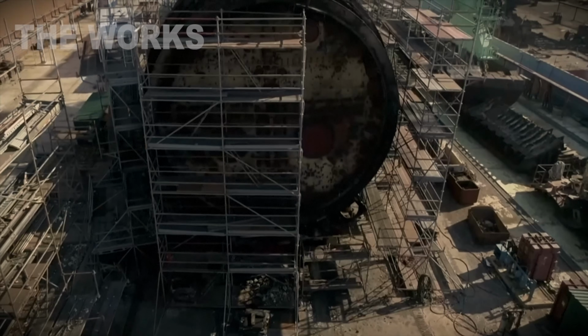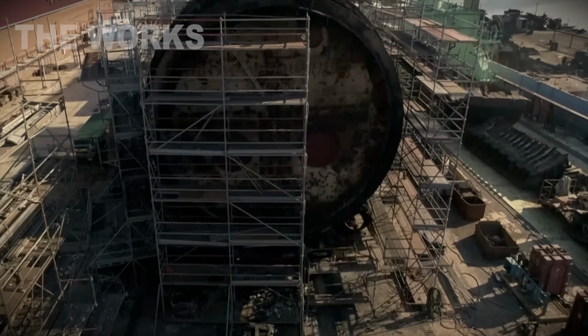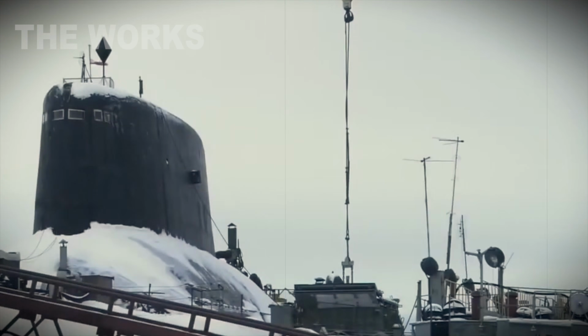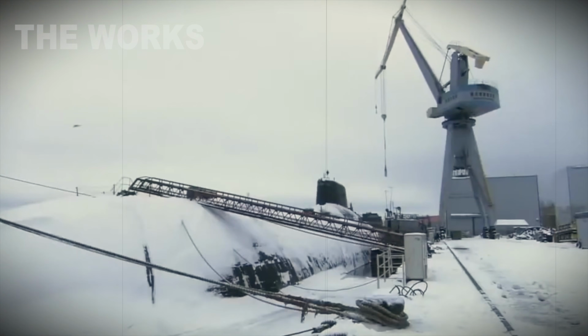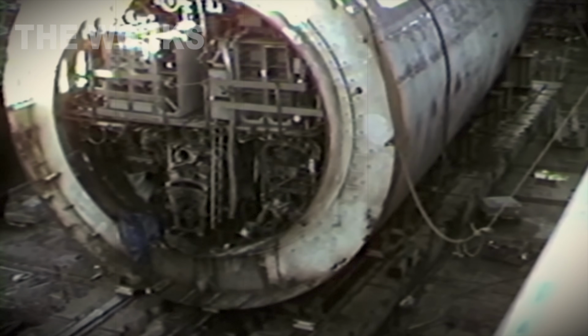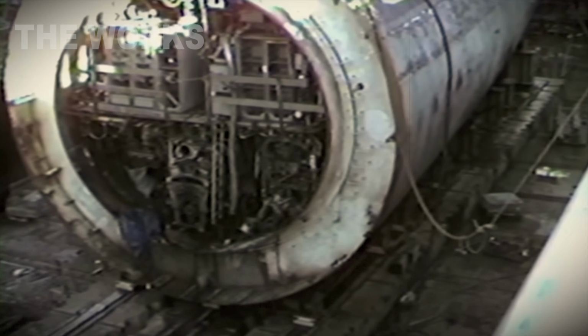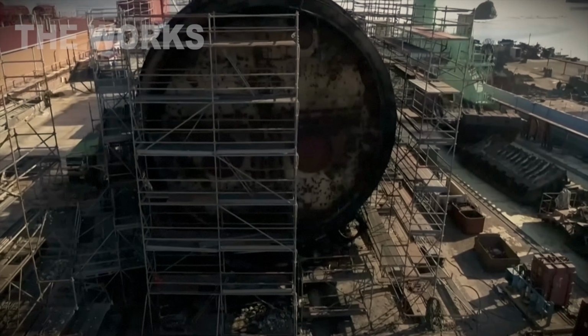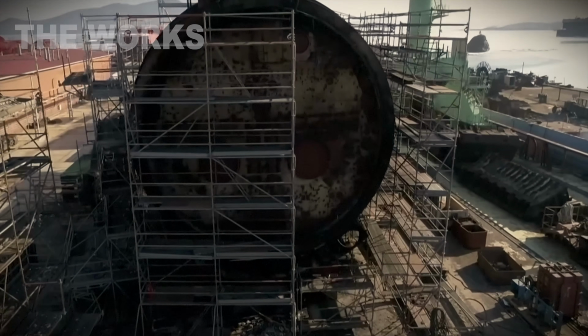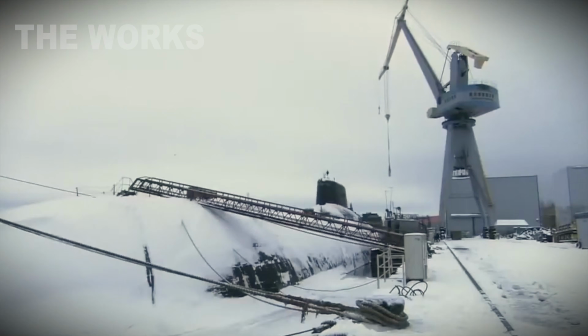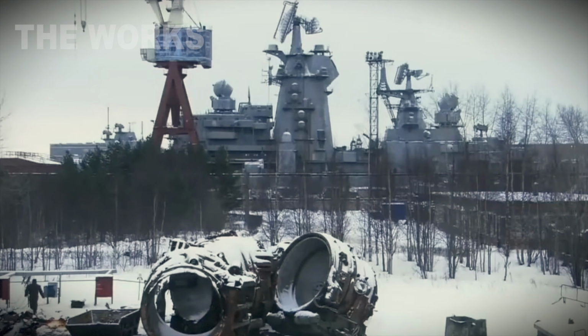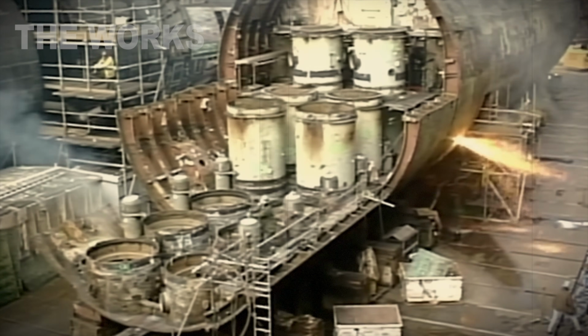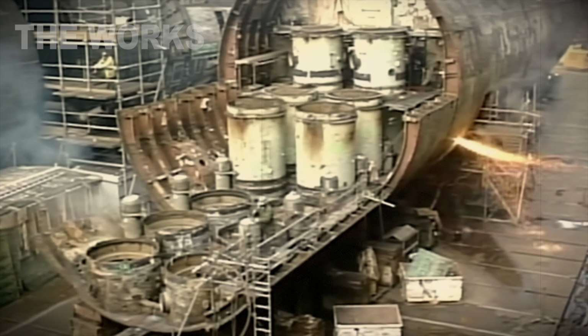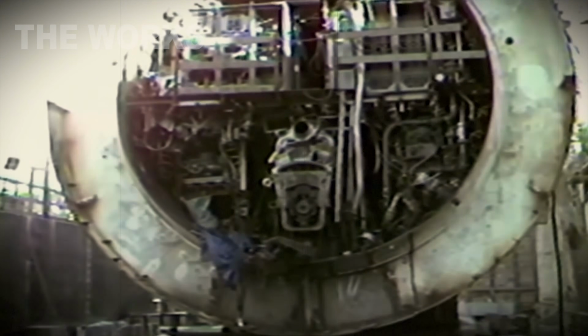Each assembly emits a lethal dose of radiation, 500 roentgens per hour at 3 feet. That'll kill a person in an hour. The assembly is lifted by a crane rated for 20 tons and lowered into a lead container. Container wall thickness, 10 inches of pure lead. Container weight, 17,000 pounds. Only lead stops gamma radiation. The containers are loaded into special rail cars with water cooling and shipped to temporary storage. This stage takes 3 to 4 months of continuous work.